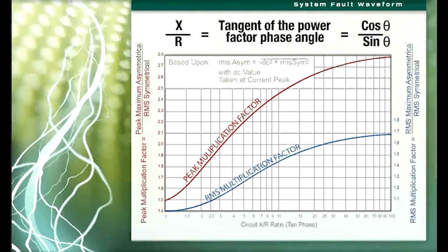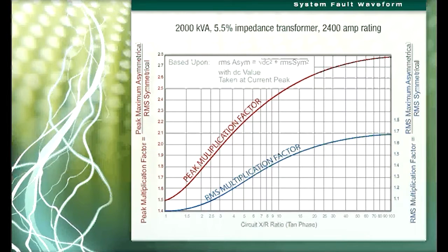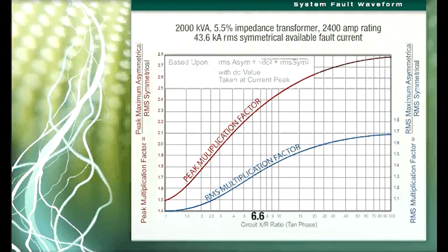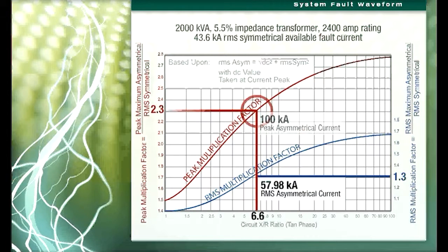Referring to the original example of a 2000 KVA, 5.5% impedance transformer with a rated current of 2400 amps, the available fault current was calculated as 43.6 kilo amps RMS symmetrical. At an X over R ratio of approximately 6.6, the asymmetrical current of 57.98 kilo amps is obtained by using a multiplier of 1.3 times the symmetrical current, and the instantaneous peak current of 100 kilo amps is obtained by using a multiplier of 2.3 times the symmetrical current.